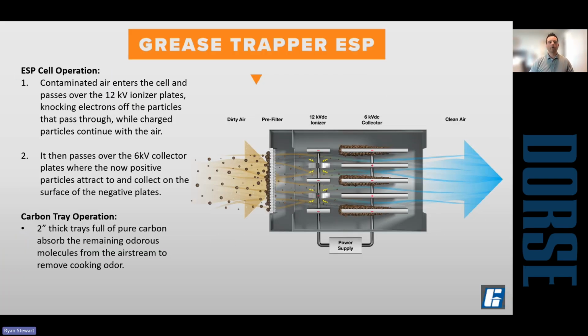So how's it work? So it's using 12,000 volt ionizer plates to positively charge the airflow as it comes into the unit. And then it passes over 6,000 volt negatively charged plates, which attract those positive charged particles. They stick to the plates. And then at the end of the day, that's what gets washed down. So you have a fresh start the next day. Again, just like the other PCU, once you've removed the grease-laden vapor and particulate, then you have carbon trays to absorb the odor.